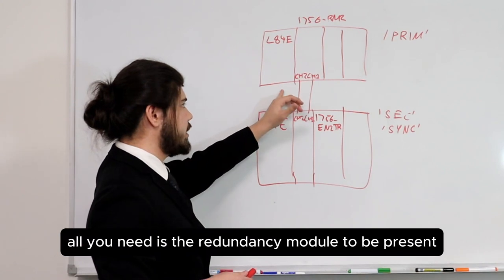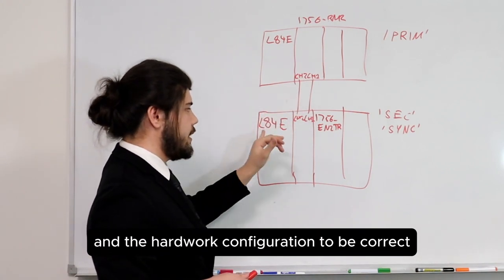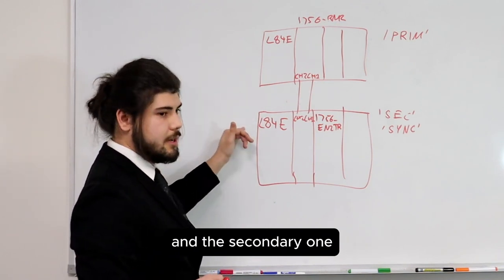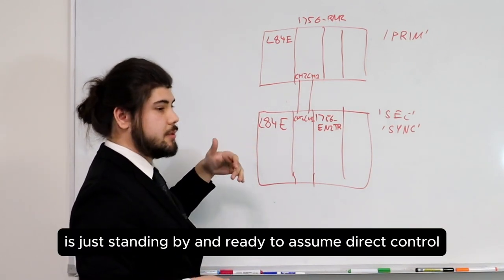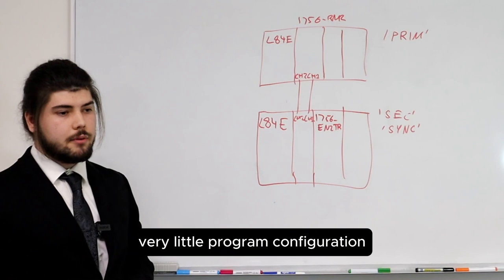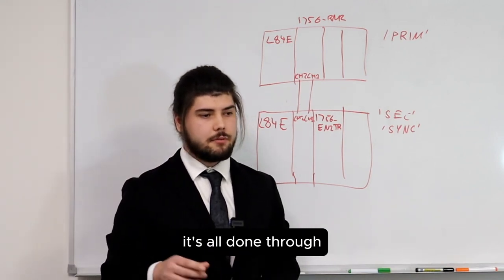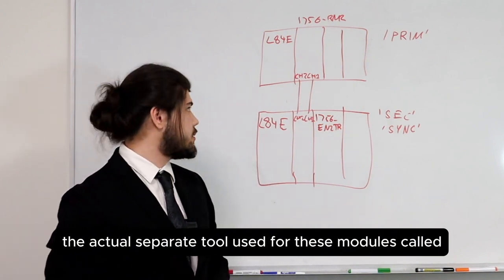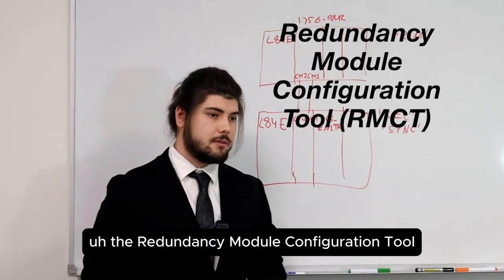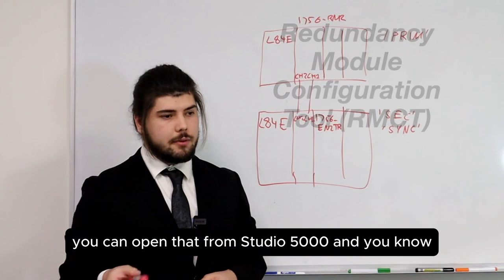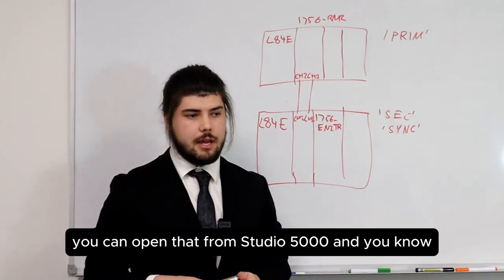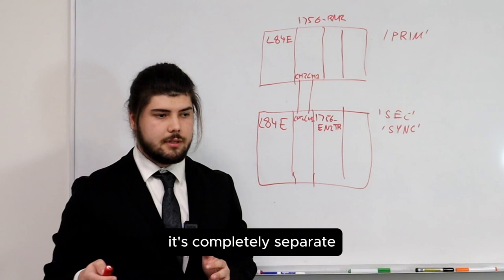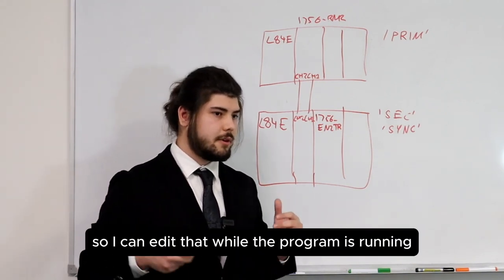All you need is the redundancy module present and the hardware configuration correct. There is no difference in the program which runs on the primary and the secondary — one's just standing by and ready to assume direct control. Very little program configuration is required. It's all done through the separate tool used for these modules called the Redundancy Module Configuration Tool, or RMCT. You can open that from Studio 5000, but it's not part of the program — it's completely separate. I can edit it while the program is running.